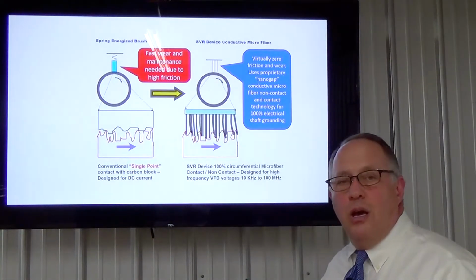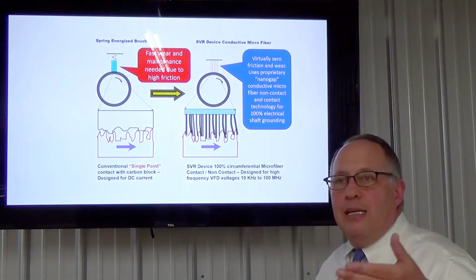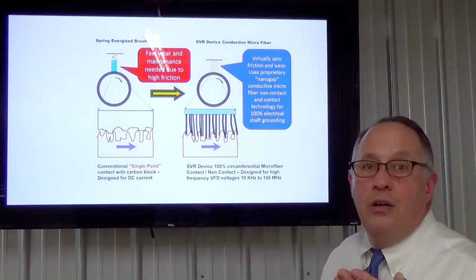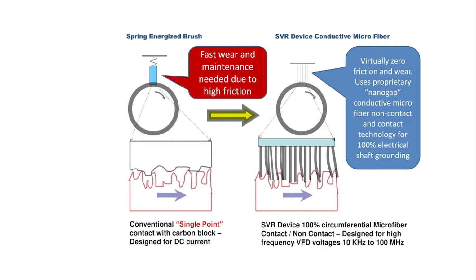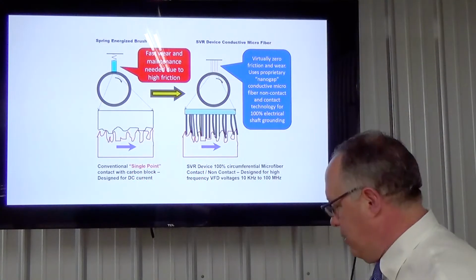SVR, shaft voltage reduction device, same thing, SGR, shaft grounding ring. Virtually zero friction and wear, proprietary nano-gap conductive fiber, which runs along the shaft itself and provides a path to short circuit any shaft voltage directly to ground. These provide 100% circumference microfiber contact and are designed for high frequency VFD voltages from 10 kilohertz to 100 megahertz. These other shafts, just to call it out, are generally designed for DC type current.